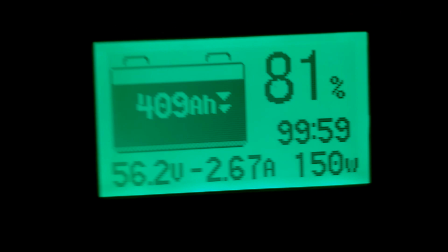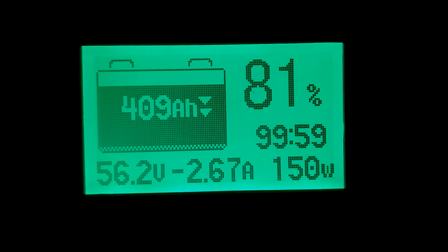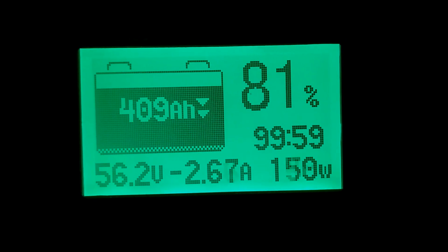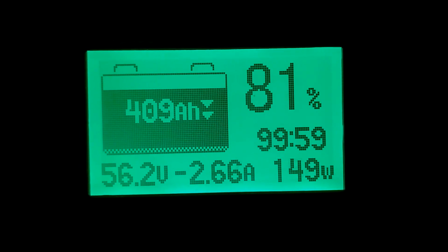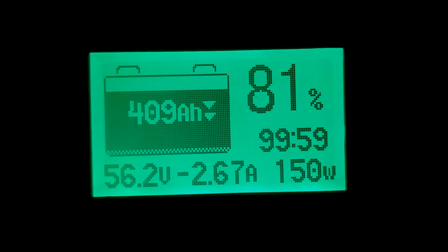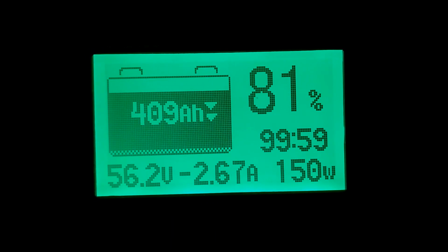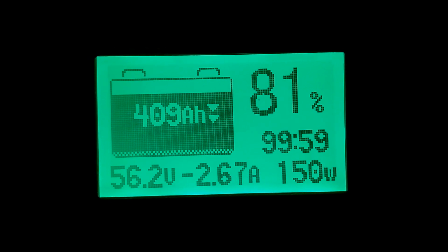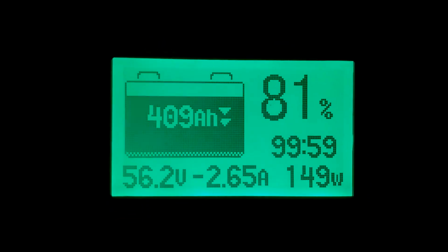These units are using 150 watts, so about 75 watts apiece, when they are not exporting any power out. So let's see what it'll be if we put them into standby mode. Hold on a second, let's put it in standby mode and we'll see what it's doing.